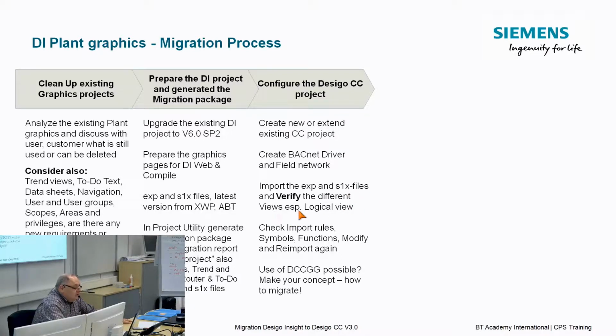Then verify the different views, especially the logical view. Then check import rules. If you are using customized import rules because you have a customized PX solution library, then use the same customized import rules here too. And then, depending on the result you're having with the graphics, maybe you might use the Desigo CC graphic generator tool to do it, or you do the migration, one or the other.